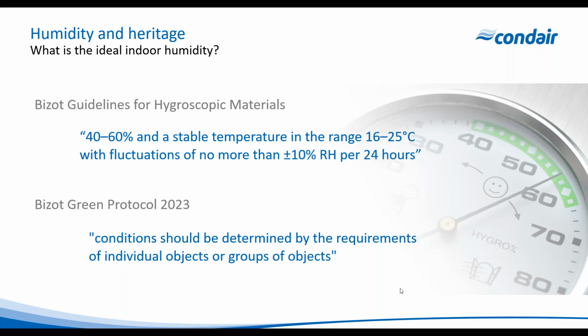And the most recent publication of the Bizot Green Protocol, which is a leading voice on the matter, in 2023 highlighted this, with its view that the 40 to 60% range is really a starting point. And although the 40 to 60% range and 10% drift are still endorsed, the actual set points are at the discretion of the conservator's evaluation, and should reflect the needs of individual exhibits in a more nuanced way. This ultimately offers a more sustainable approach to the environmental control and conservation with a green first approach, but understandably, this is a more difficult goal for facility managers and HVAC professionals to deliver against.